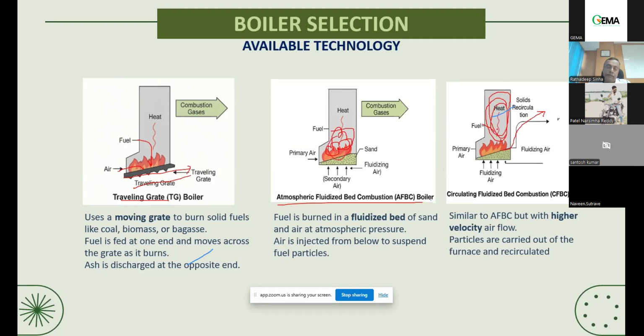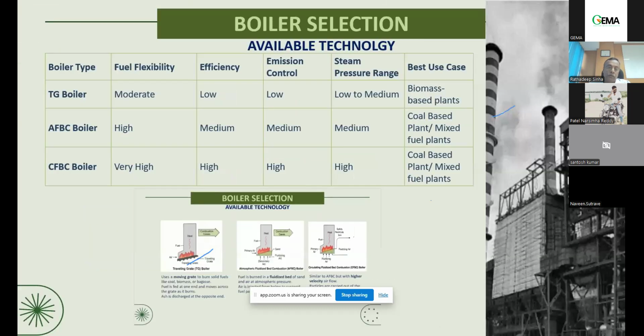We find that between AFBC and CFBC boilers, there will be an efficiency difference of around 1.5 to 2.5%, depending on what kind of fuel we are going to burn. So the question is, what technology should you select as a buyer? If you see the TG boiler, the fuel flexibility is moderate. So if you decide to run the plant predominantly on biomass, and the fuel is more or less decided, like bagasse or something like that, then you decide on a TG fired boiler.